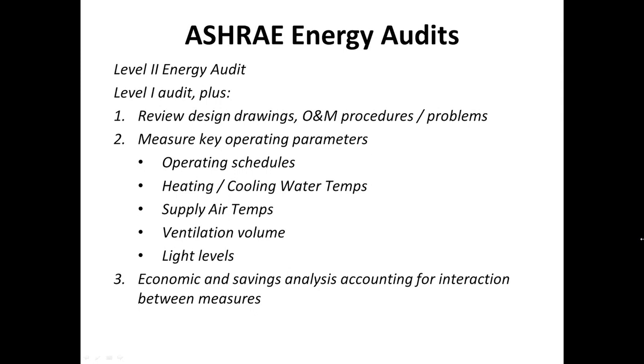So the level 2 really builds on a level 1 audit. It's still looking at those operating parameters, but it's also looking at low-cost measures, maybe that fall within a 5-year payback period. This is where you start to actually look at and collect data, looking at supply air temperatures, supply and return water temperatures, operating schedules, and doing a little bit more in-depth analysis and giving some financial perspective on measures other than operation and maintenance that can be addressed in the building.